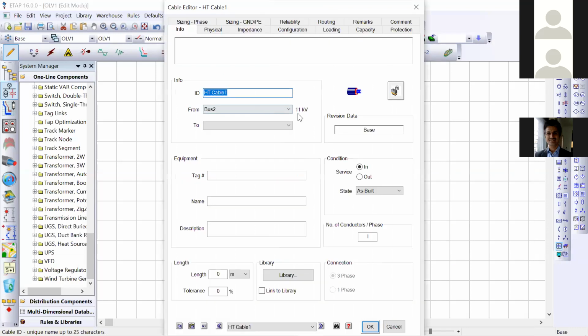So the relevant parameters it will take automatically, like it is connected with bus bar 2, which has got an 11 kV source. So I don't need to give instruction to ETAP that it is connected with the 11 kV source. It is taken automatically. Once the source is confirmed on 11 kV, all the down-the-line elements are taken on the same voltage level. Now for any cable, we need to enter the length. So 10 meter length, a short length of cable between the power grid meter and my transformers. I can take a tolerance also.